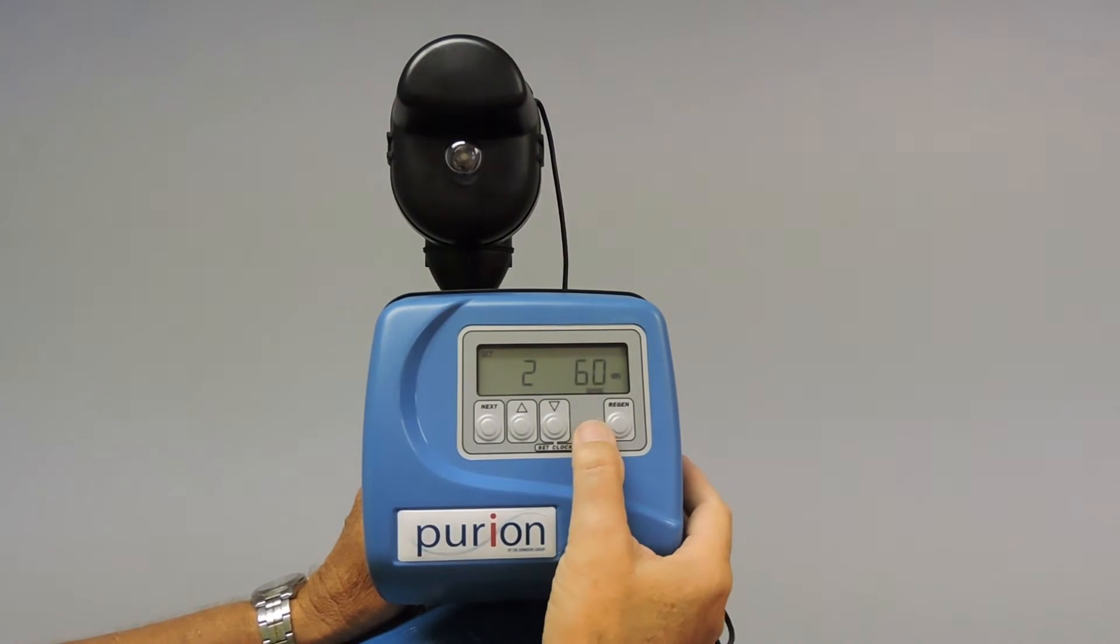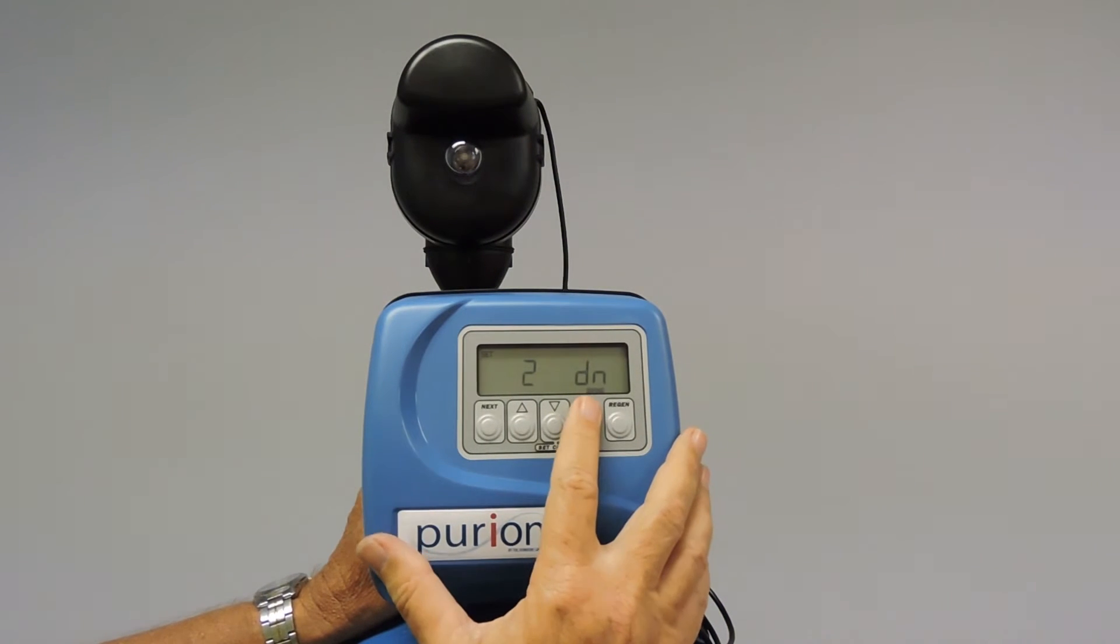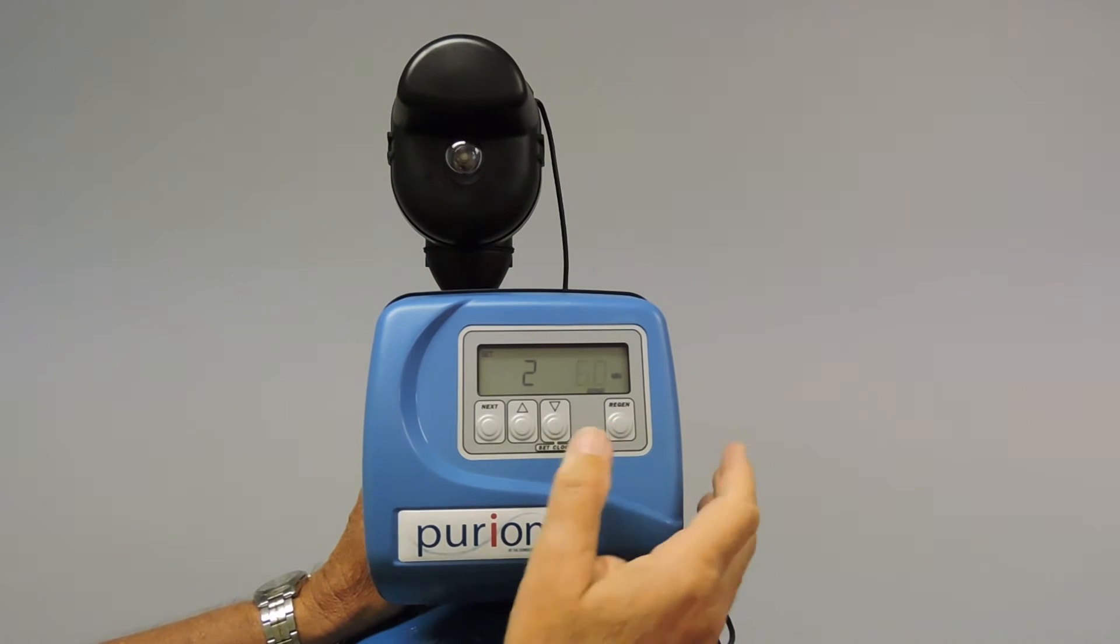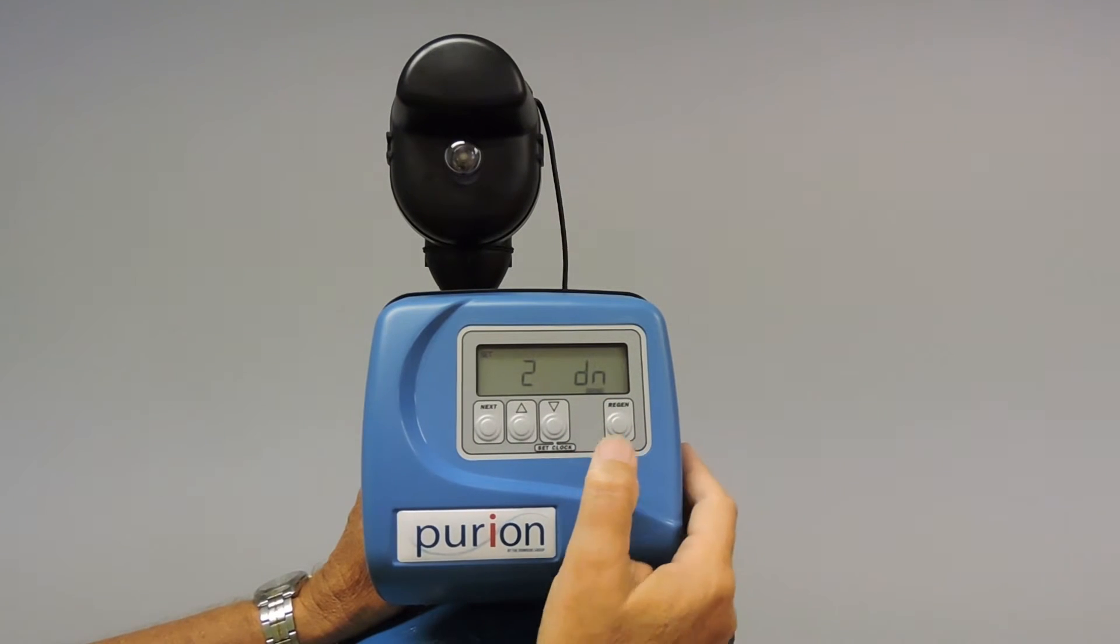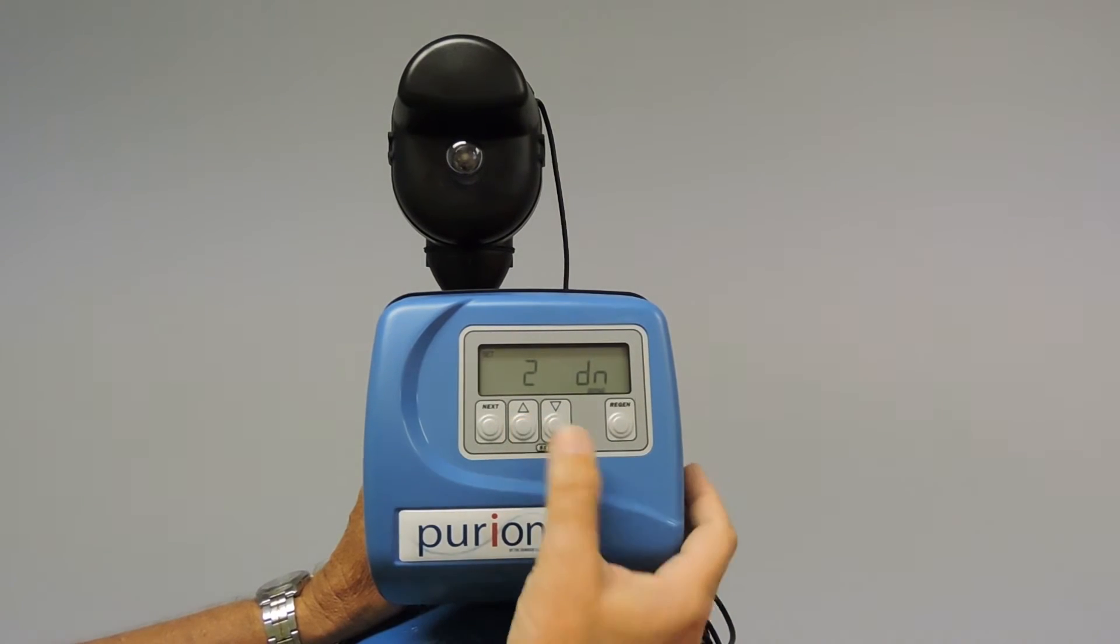We're now into the second stage which is our brine draw and slow rinse cycle. And we're using a down brining sequence. We pre-calculated our 12 inch unit is 60 minutes of time required. So we will simply arrow up.